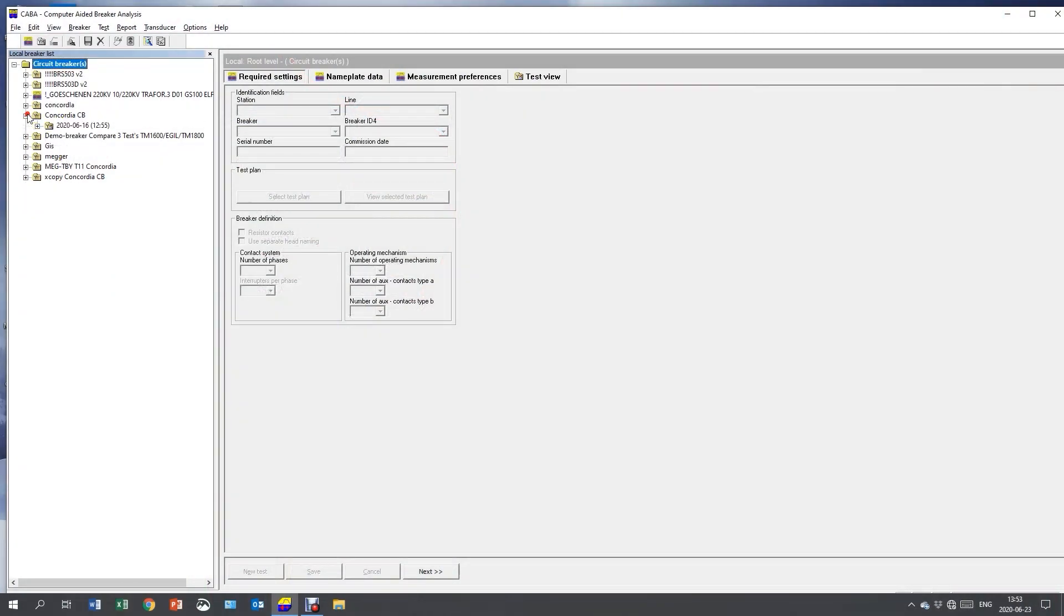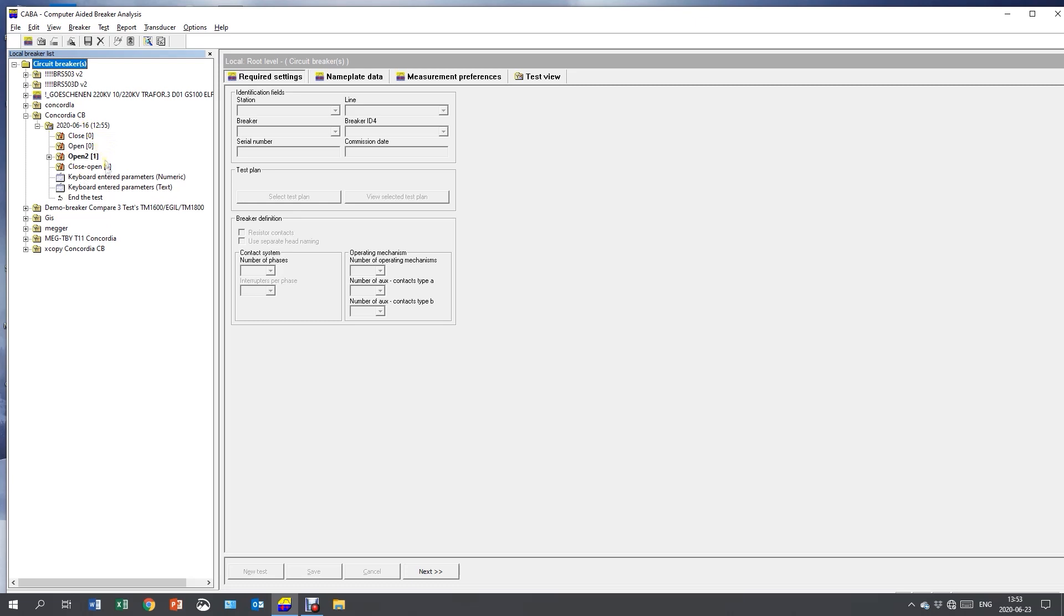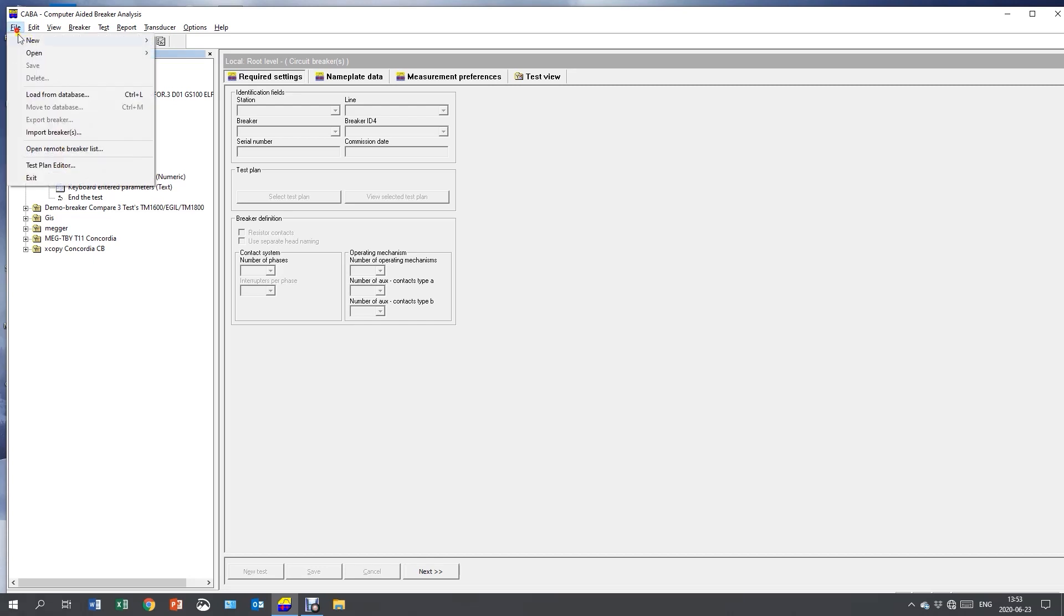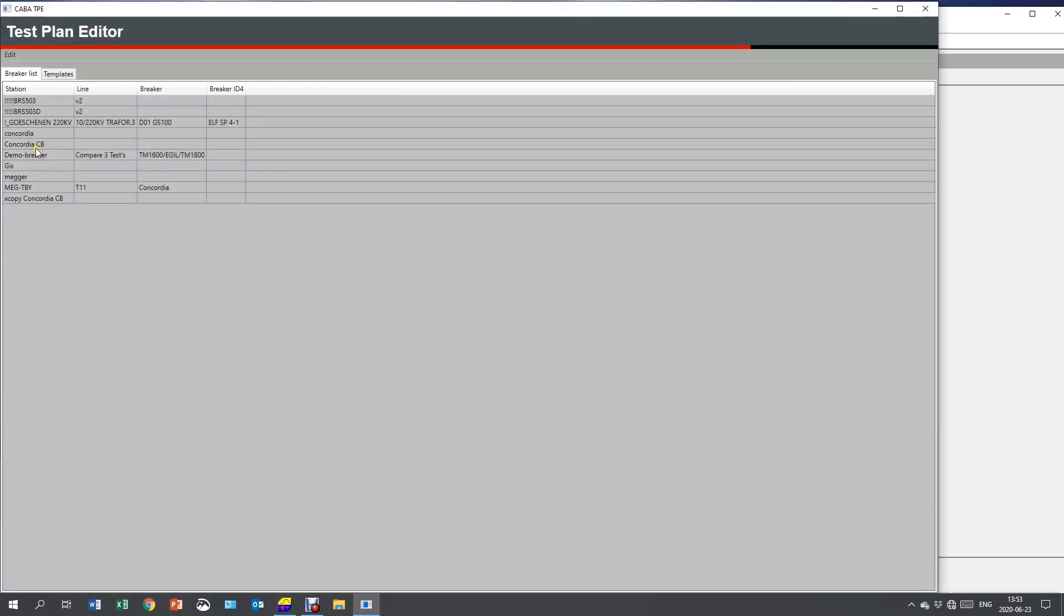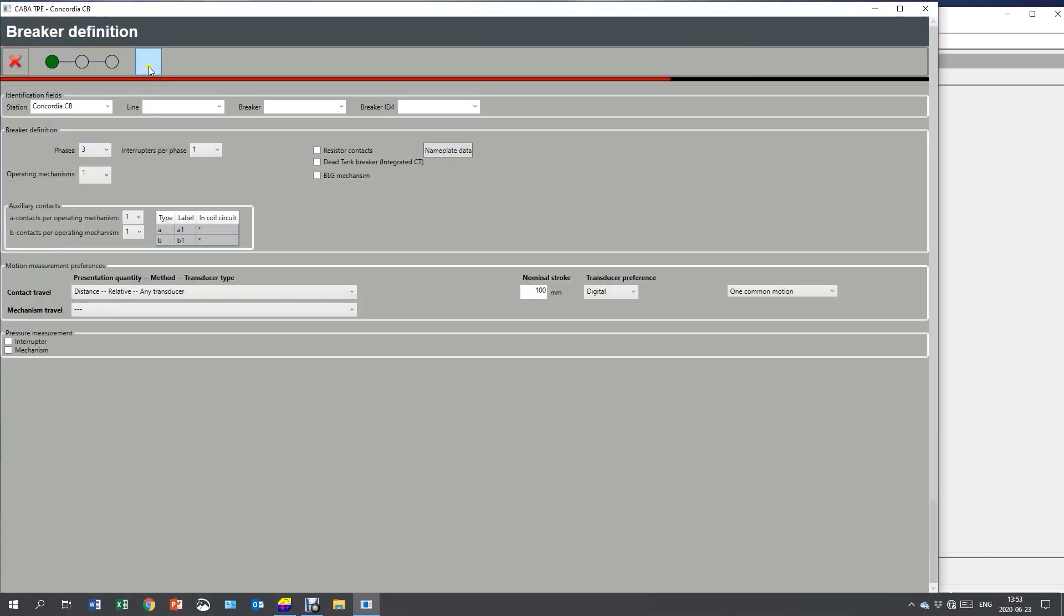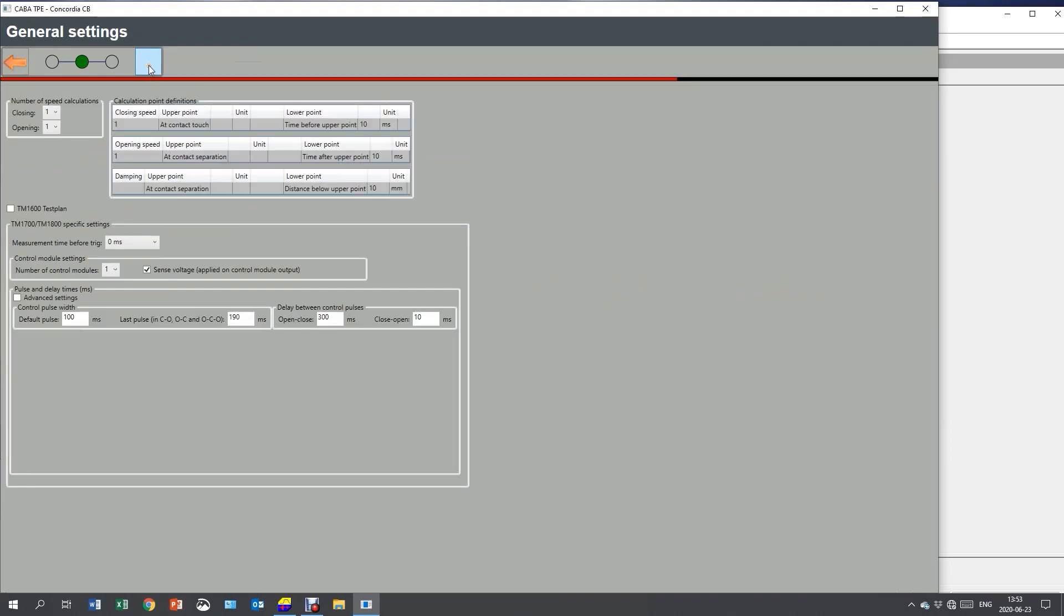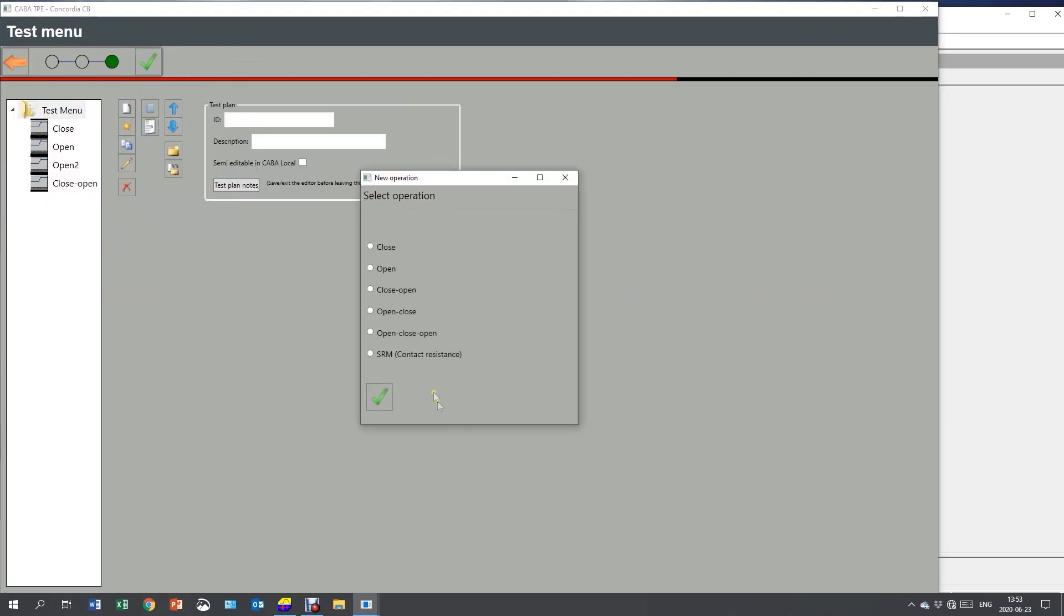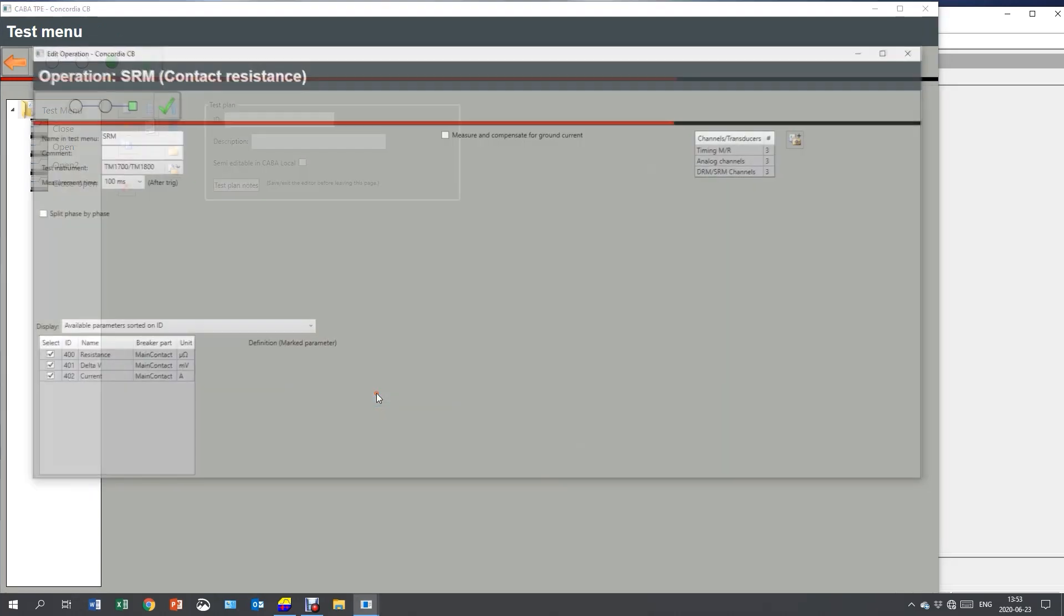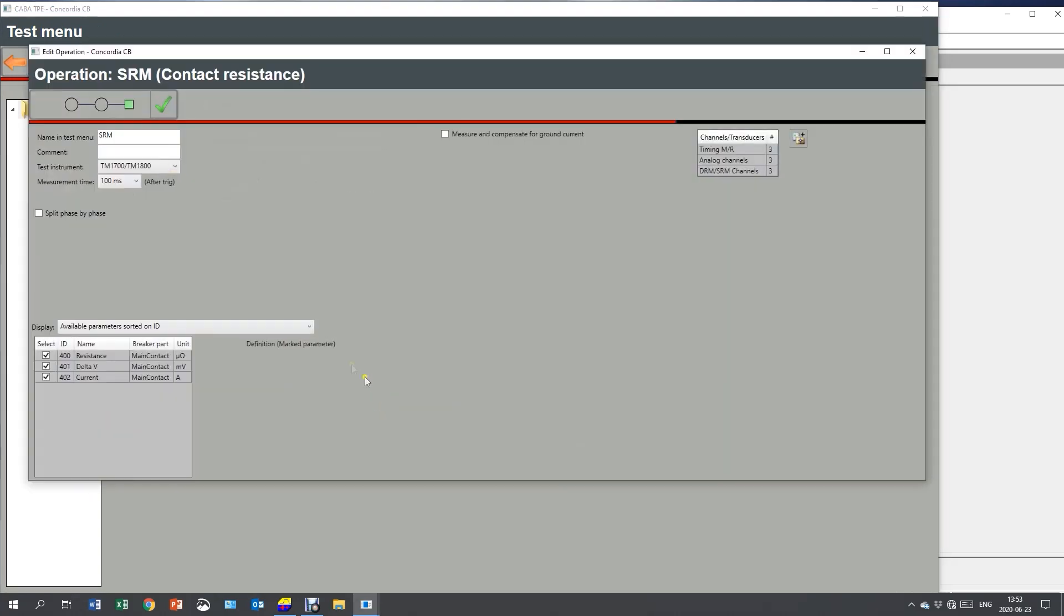Here I have my circuit breaker. And as you can see, I don't have my resistance recordings in the menu. So I need to add SRM and DRM in my setup. I go to the test plan editor and I start changing my setup. I need to add the SRM to my menu.